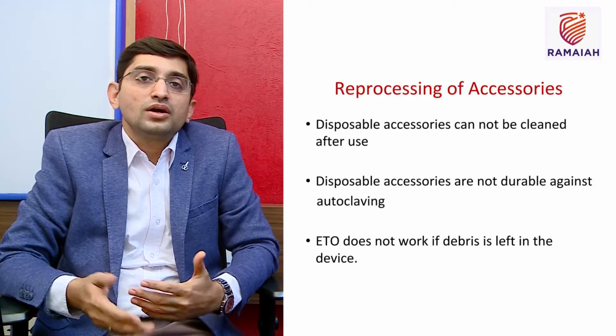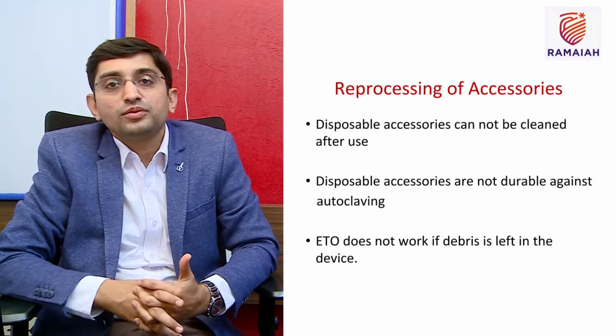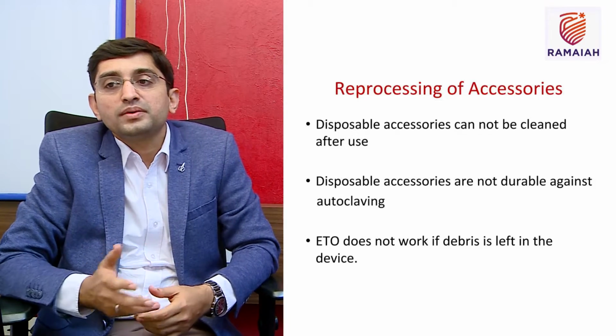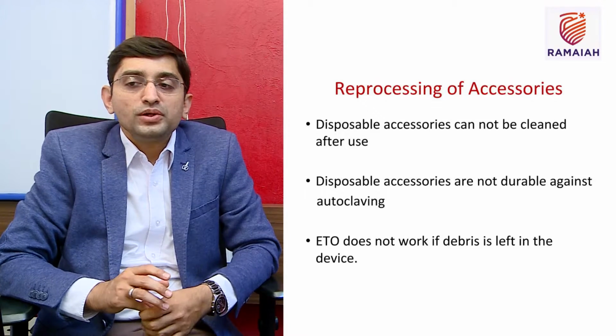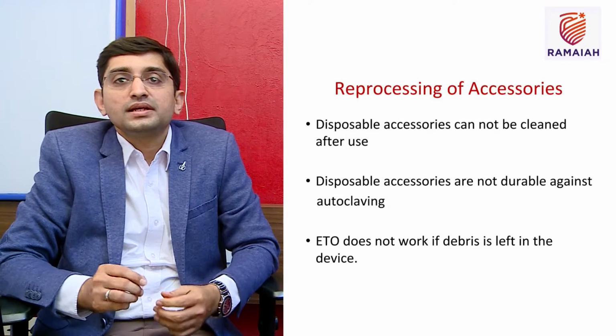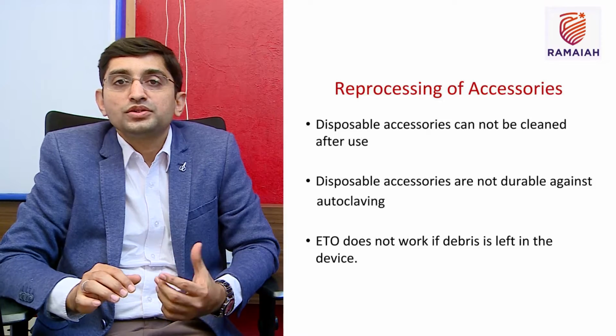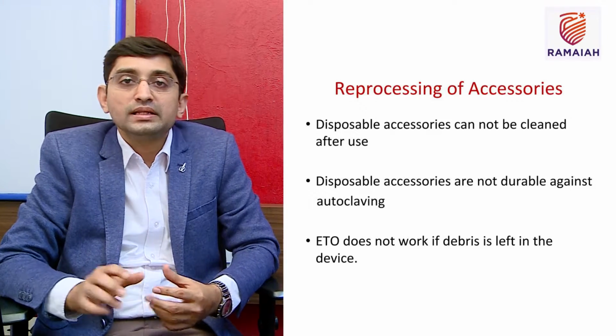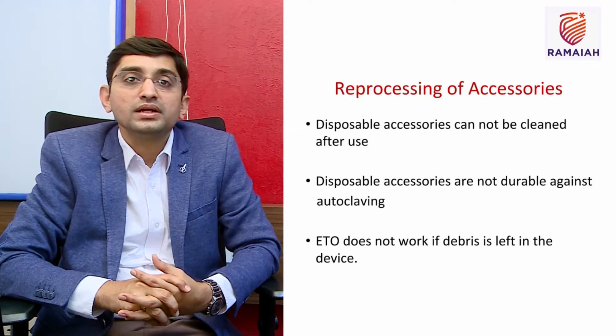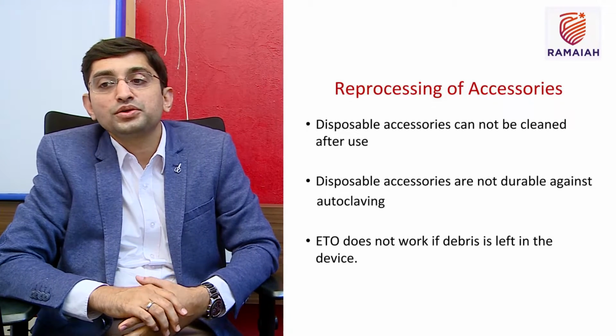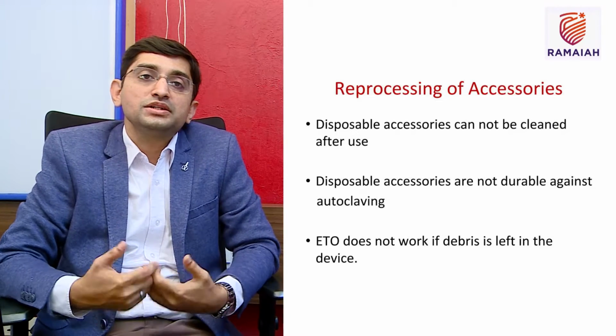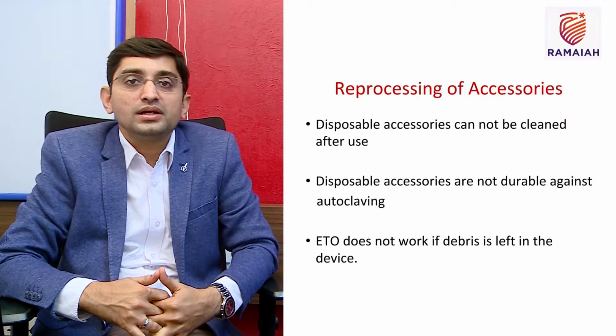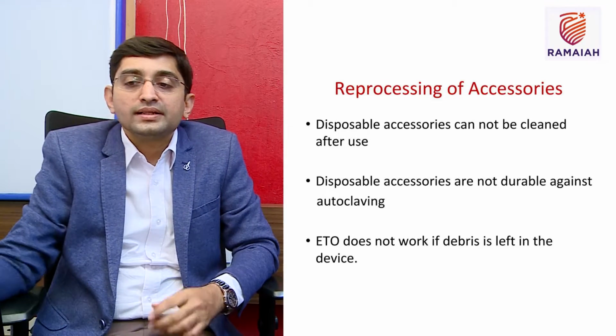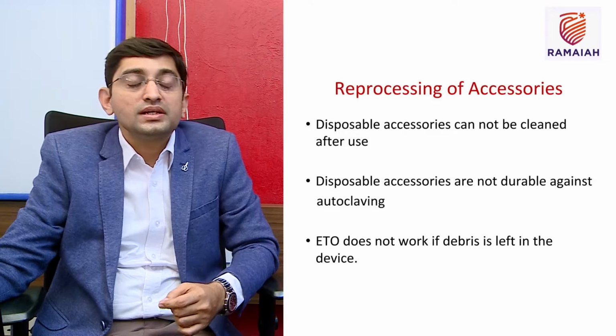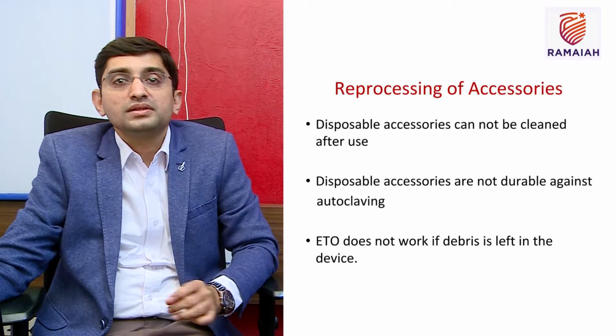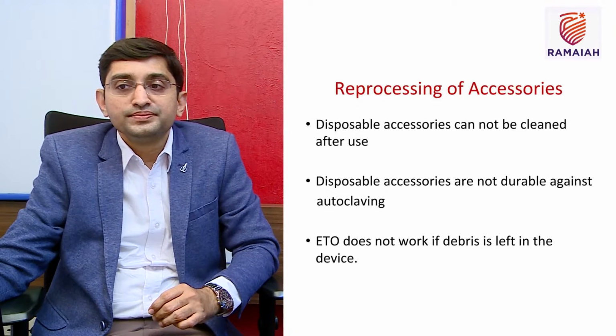So we tend to always reprocess by either ETO method, that is ethylene oxide, or by autoclaving. The most important thing is that each accessory, like the sphincterotome, comes with a metal wire, so we should always bow the sphincterotome and then clean the metal wire completely, because that's where the debris can be. Whenever there is debris, the sphincterotome may not function, and the durability after autoclaving might not hold. Ethylene oxide will not work if there is any tissue debris of the patient within the accessory.